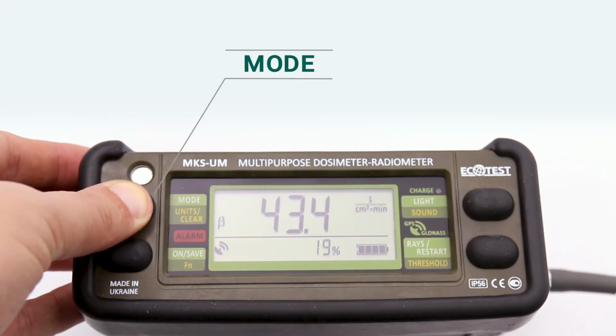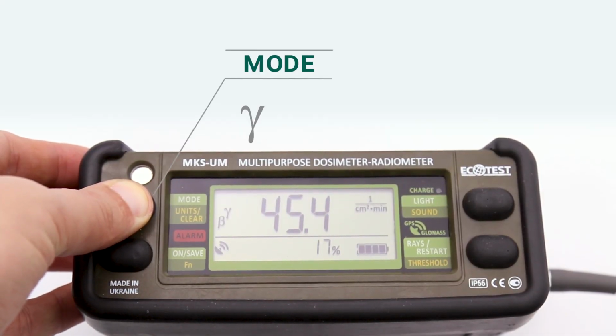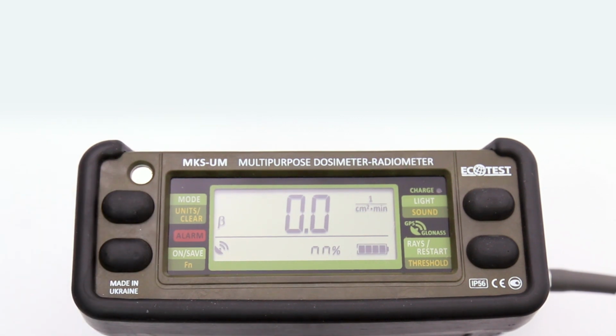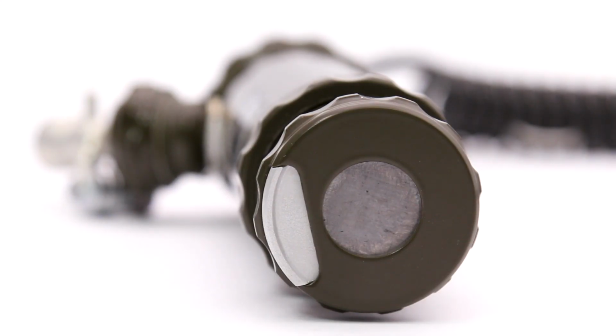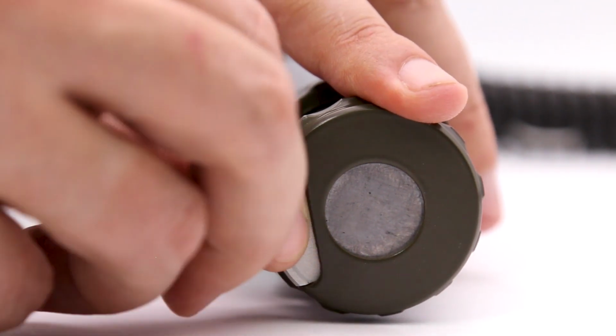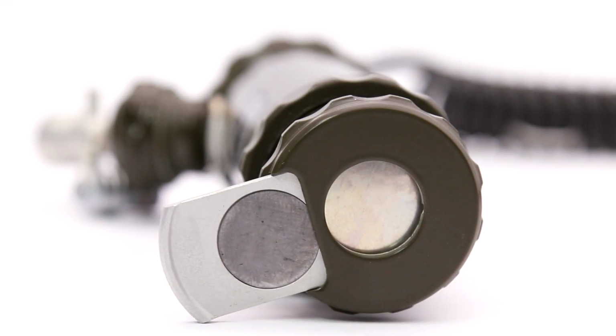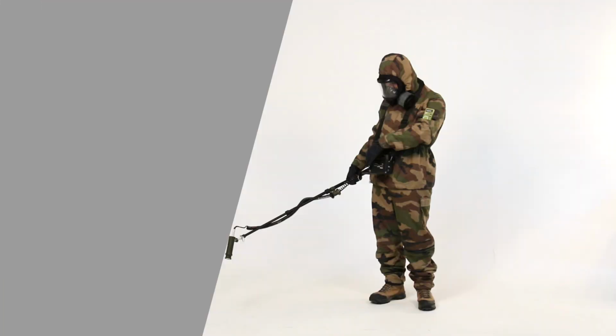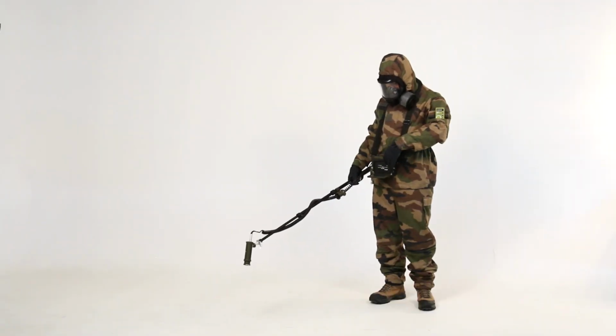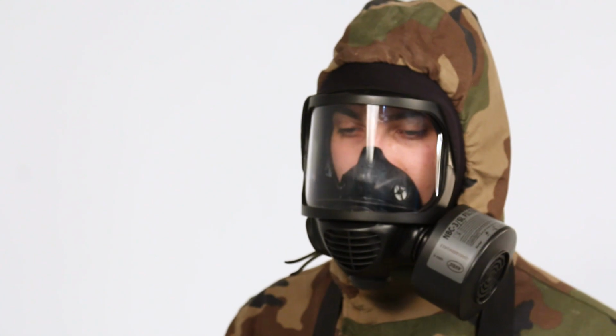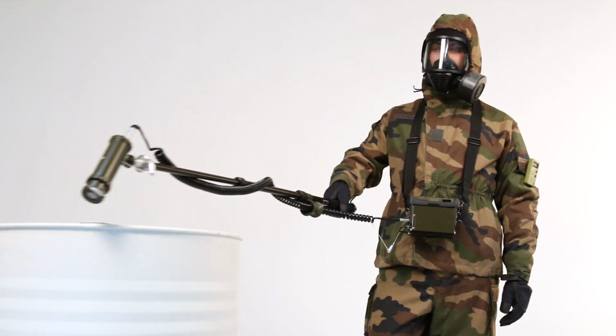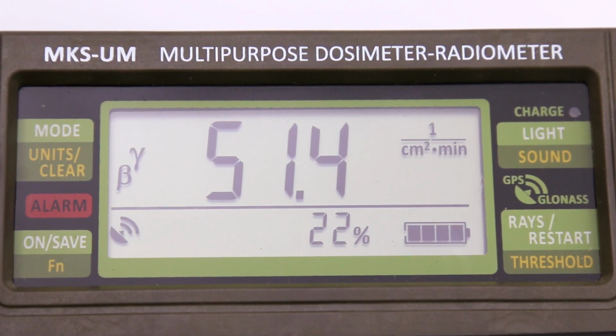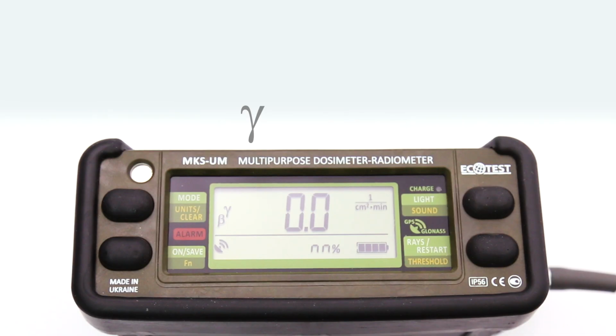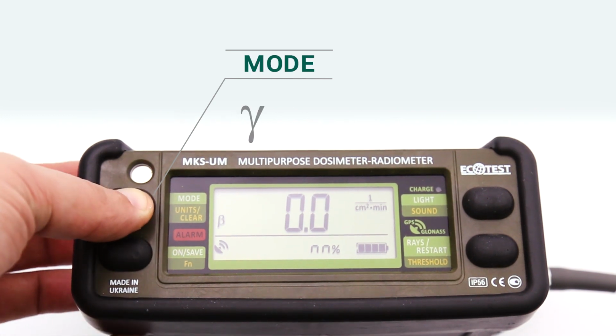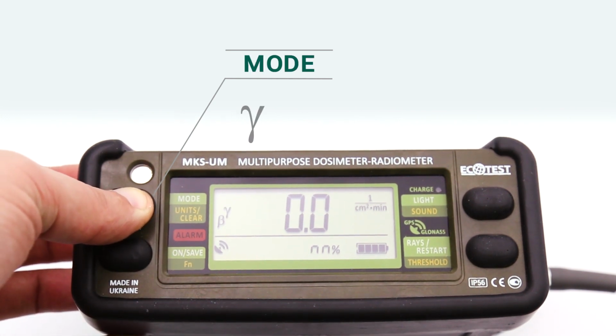To record the results, press and hold Mode until the gamma symbol flashes. The next measurement should be carried out with the beta detector window kept open. This will be the final measurement result. When changing the inspection object, reset the saved gamma radiation value. Make a new measurement and record its value. To reset the saved gamma radiation value, hold Mode until the flashing gamma symbol disappears.